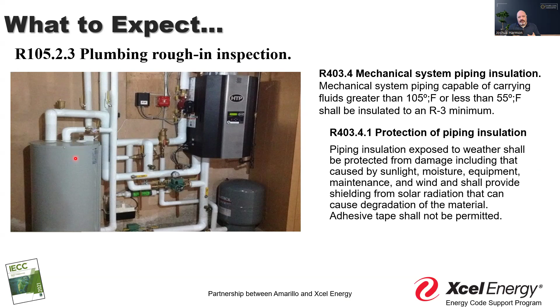That also drives this conversation: if I have a gas-fired 40-gallon service water heater coming in at 40,000 BTU, and my wife decides she wants one of those instant hot, on-demand heating systems, I need to make sure it's plumbed properly and that I have adequate gas pressure, that the line servicing it can support it, and that the meter can meet the demand. Going from 40,000 BTUs to 200,000 BTUs is an easy jump, and I've seen systems even in the 300,000 to 400,000 range. That pipe wasn't designed to carry that much gas.